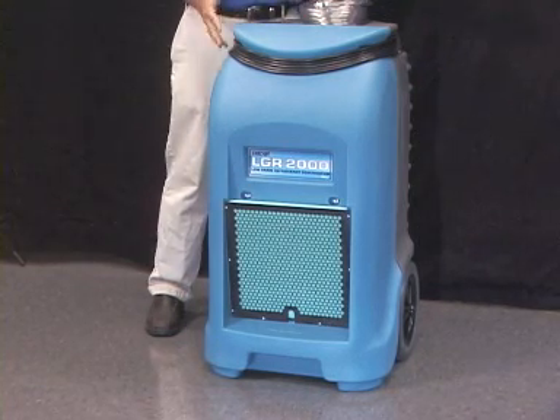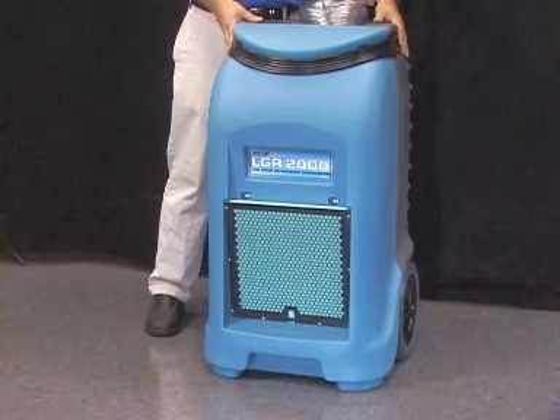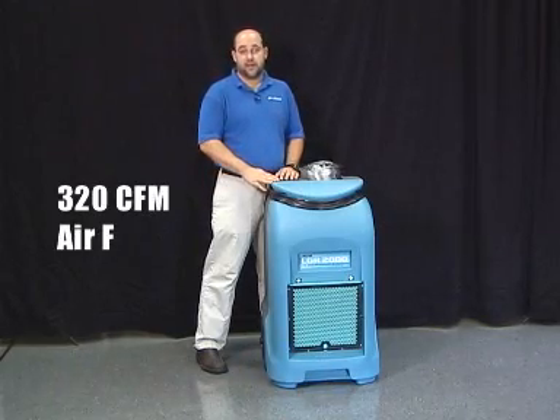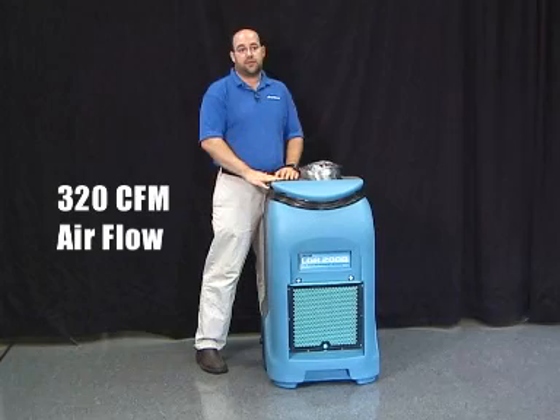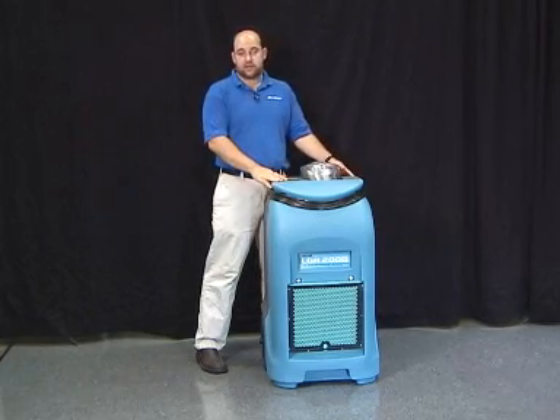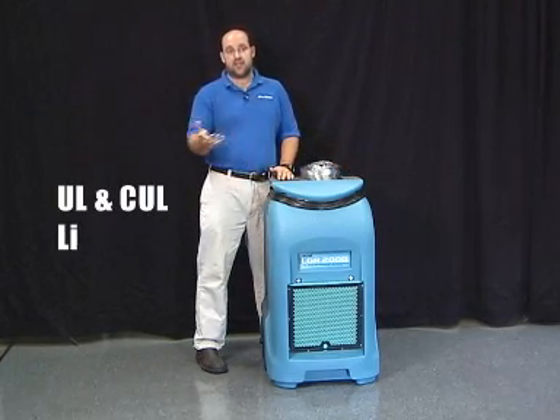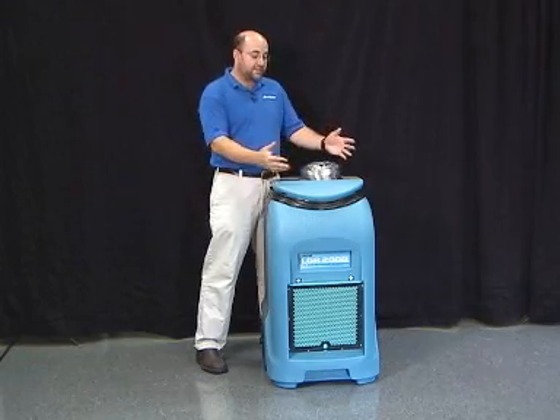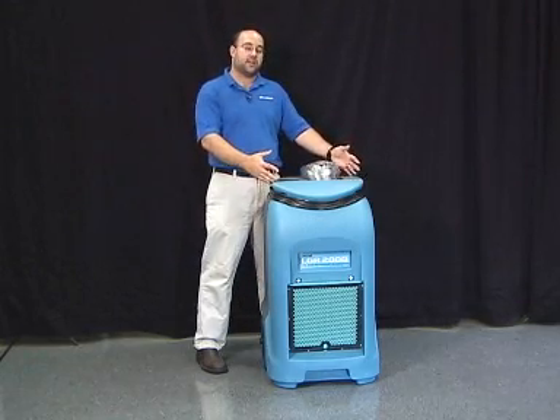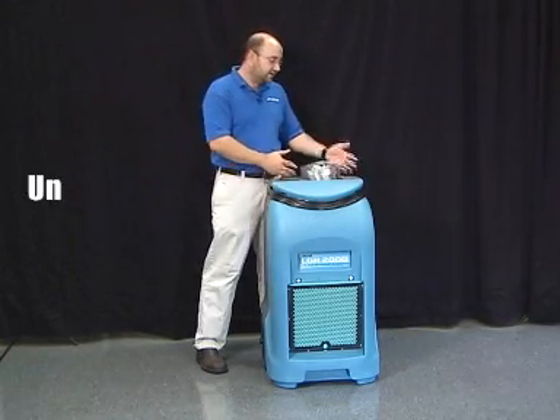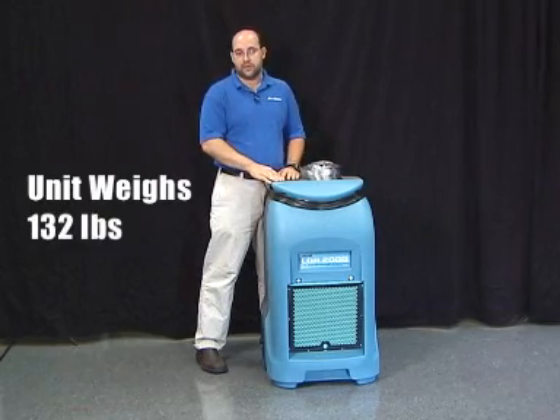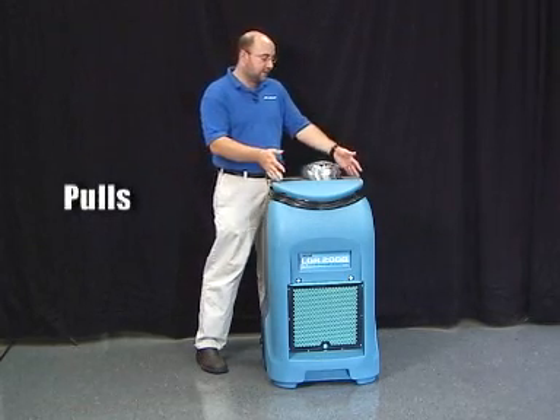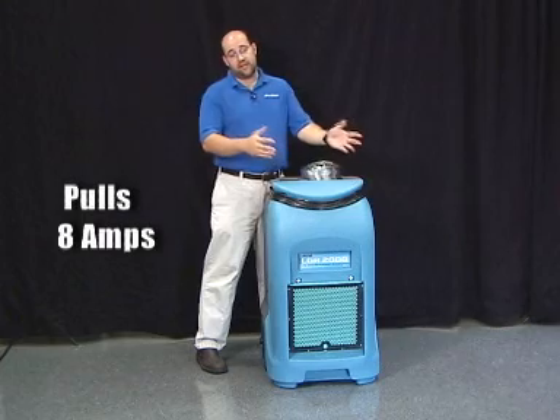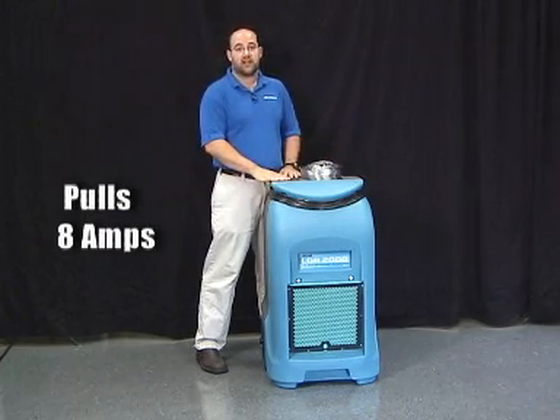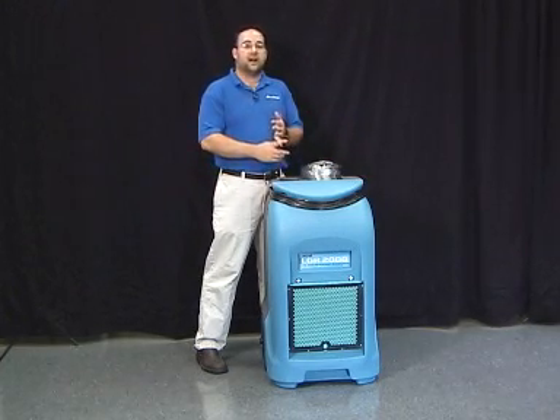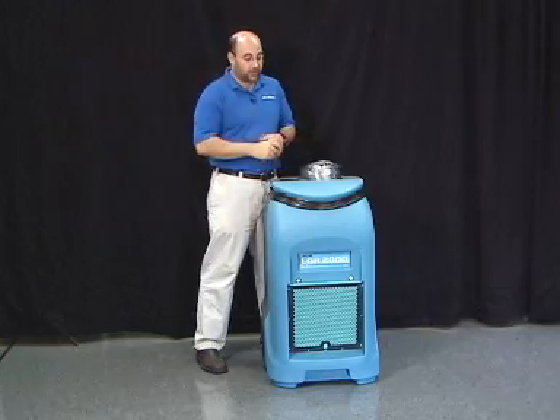The blower on the dehumidifier has the capacity of processing 320 CFM, cubic feet per minute of airflow through the system. The 2000 is UL rated and is also CUL rated. The weight of this system is going to be a little bit more than the smaller dehumidifiers. This system is 132 pounds. The power consumption, this machine pulls 8 amps, so you still have roughly 7 amps available on your circuit, maybe for an air mover or possibly even 2, depending on what you're working with.